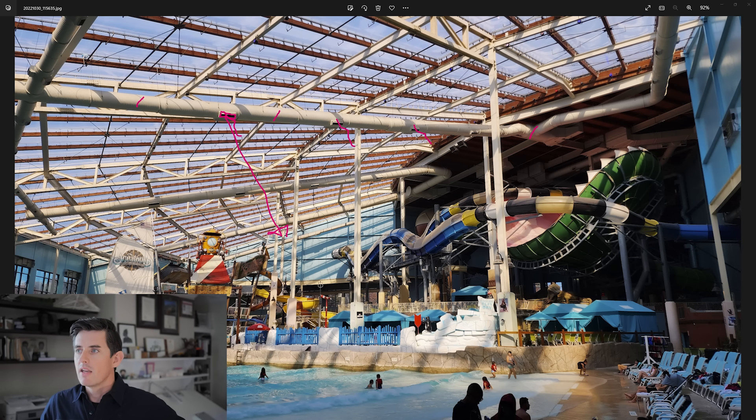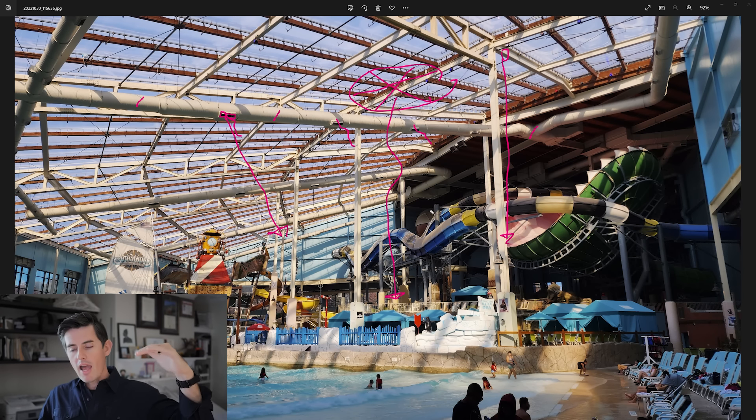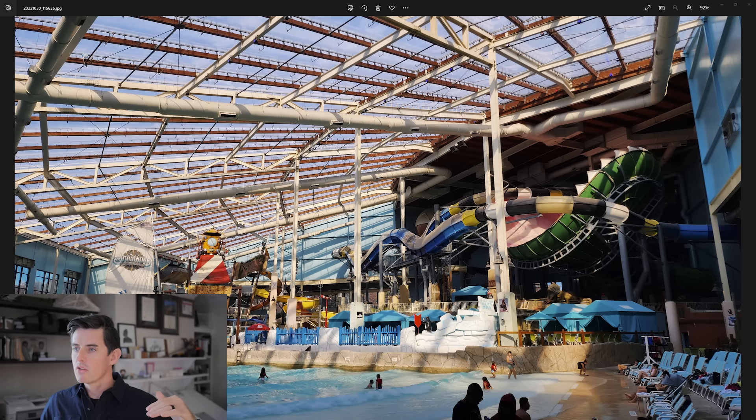I am a little surprised they didn't have some sort of low-velocity large-diameter ceiling fan to push warm air down. There are also air barrier systems trying to keep warm air at the occupant level — closer to the ground — so you're not just overheating at the ceiling level. That's one thing I noticed that was not part of this project, but there are other things to look at in terms of the building structure.